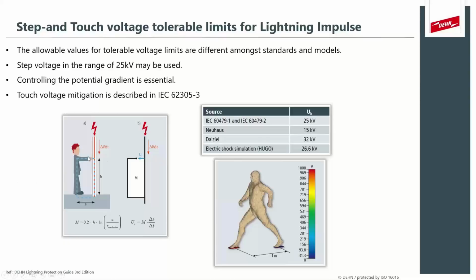So for touch voltage, when lightning passes through a conductor, it will pass through the human body into earth, where the voltage is different. But if we merely insulate a down conductor with normal insulation, like PVC pipes or things like that, that also will not suffice. The standard says that this insulation must be able to withstand 100 kilovolts of flashover voltage.